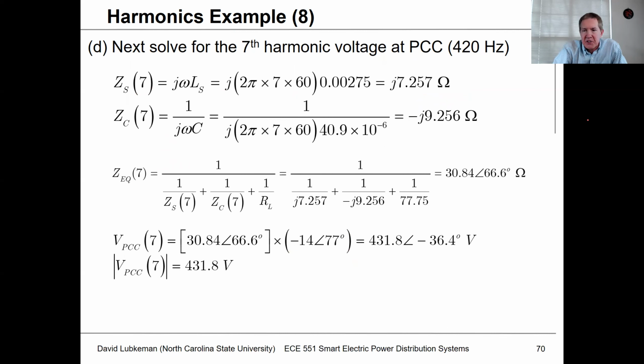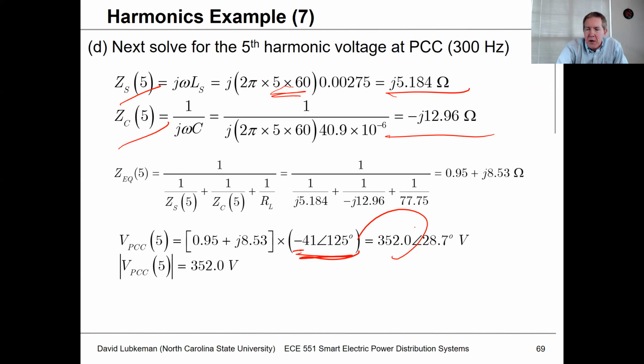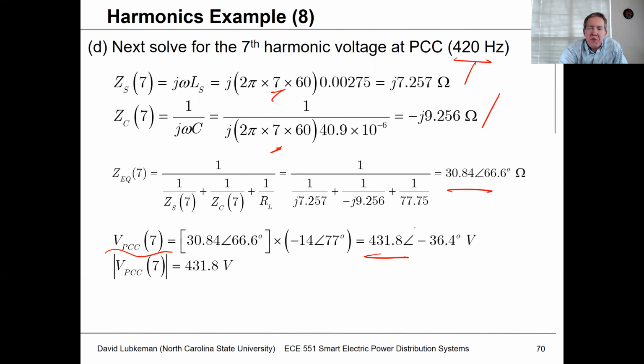And then if I look at this at the 7th harmonic, at 420 hertz, I do a similar set of calculations for the 7th harmonic. You see the equivalent impedances change at the 7th harmonic. I come up with a new equivalent impedance. And then when I calculate the voltage at the 7th harmonic at the point of common coupling, this is going to be 431.8.